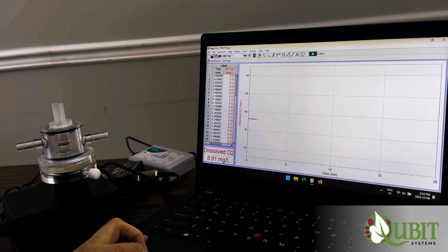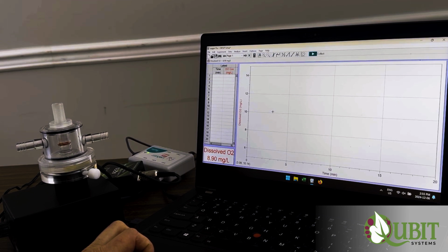We've got some old data here. I'm just going to delete this data, clear all data, so we have no data in the file right now. And you will see the current dissolved oxygen reading shown in this meter. If we click collect and start collecting data, you will see the data being populated in this table, and you'll see the graph starting to show a trace as well. But before collecting data, I'm going to stop this collection. I want to go through the calibration process, which is what one should do before using the electrode. So let me just delete the data by going to data, clear all data.